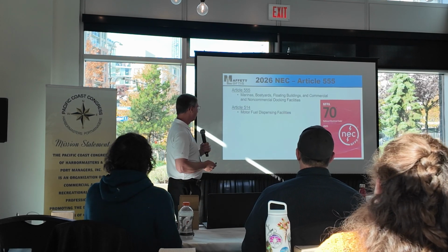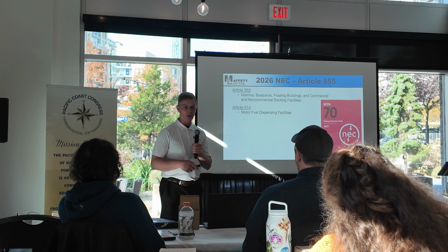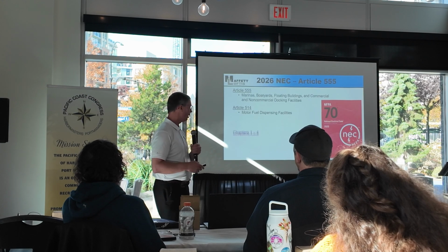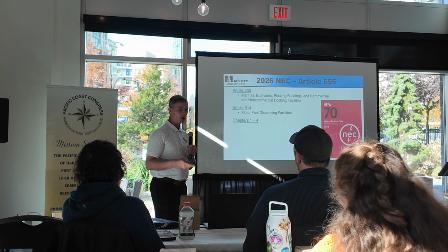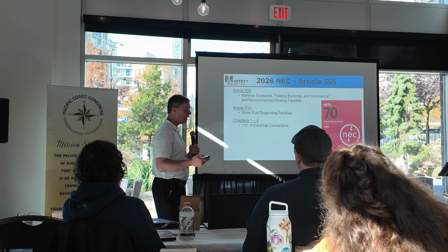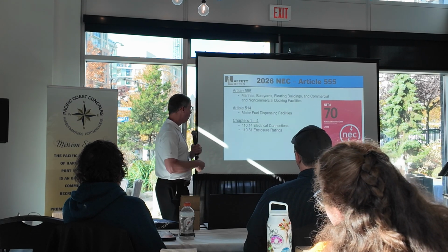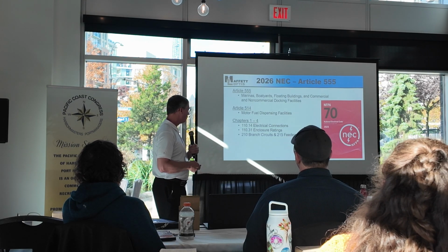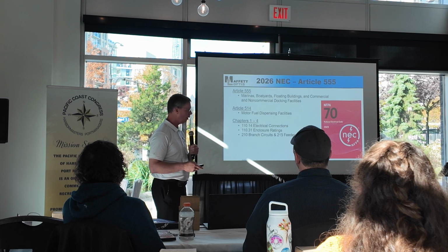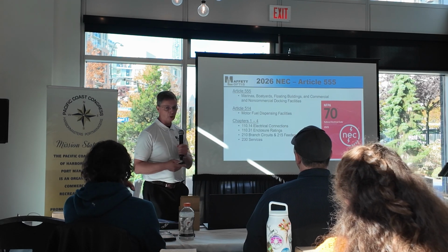Because if you have, for example, a fuel dock, we go to another article, 514, to do with that. Chapters 1 through 4 also apply. If you have electrical connections, it's 110.14. If you have electrical enclosures, it's 110.31. Branch circuits and feeders, 210. All marinas have a service, it's under 230.